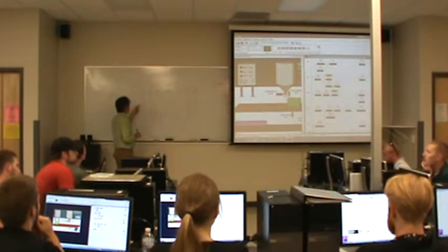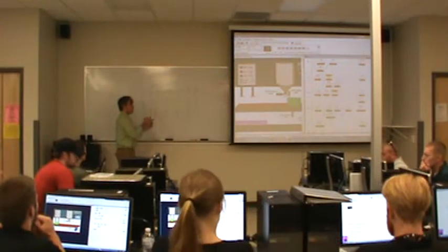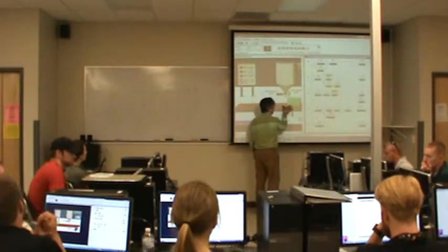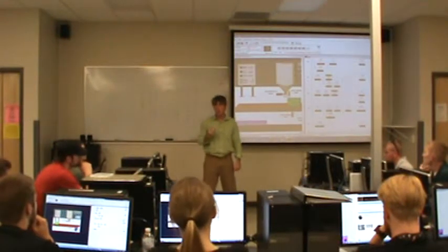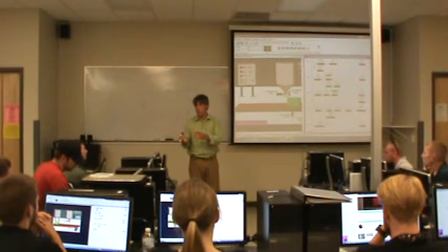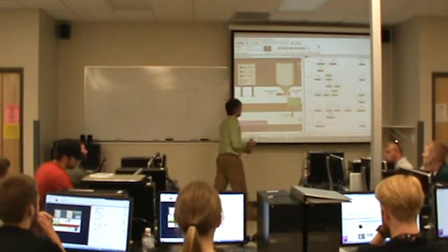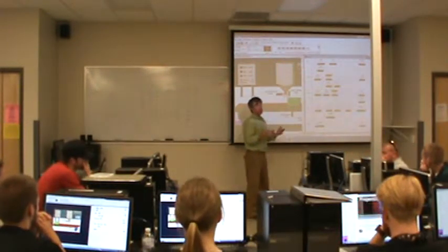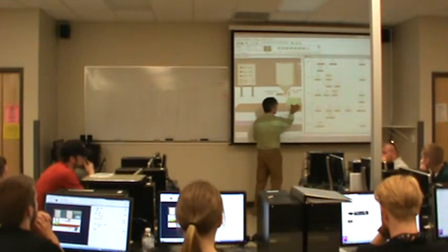What else? Well, when the full bit is true, prox is true, and level is true, that's only going to happen for a short period of time, because that's the time when the box has been sitting under here, it's full, and now the full bit has been triggered, and so the box is now moving. Now, another trick to PLC programming that's very important to remember is that you need to think in terms of what's going on in the PLC speed versus mechanical system speed. Mechanical system speed is typically much slower than the PLC speed. So the PLC is going to feel like it's waiting forever for the box to move out of the way. It's going to say, okay, we still have a full box, new scan. Still have a full box, new scan. It's going to be waiting for a long time for this box to move out of the way.